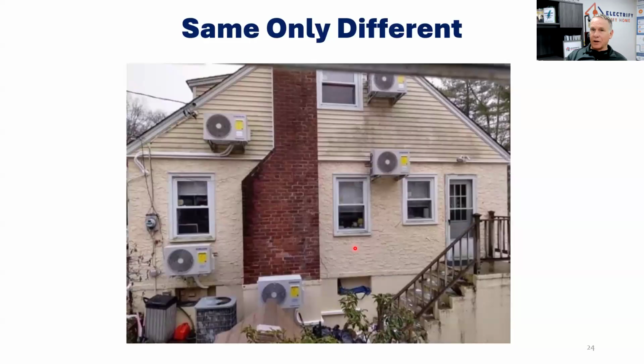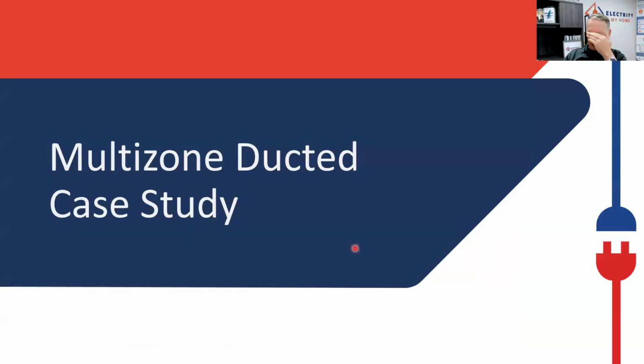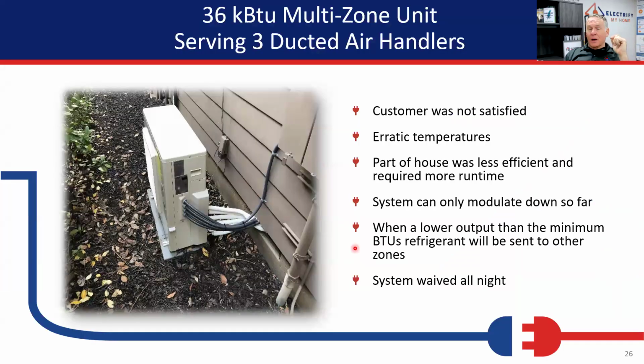It blows my mind. Okay, so here's a multi-zone case study, and I learned this one the hard way. Fortunately, it was a number of years ago. There were 3 units, a big house, 2,000 square feet, 2,100 square feet, all rancher, flat ranch house. The end of the house was the main bedroom suite. It had a master bedroom, a little tiny walk-in closet, and the bedroom was probably 15 by 15. It wasn't huge. And then there was a large open living space with the kitchen, living room, dining room all in one big space. That whole space, if I remember right, was about 12 or 1,300 square feet.